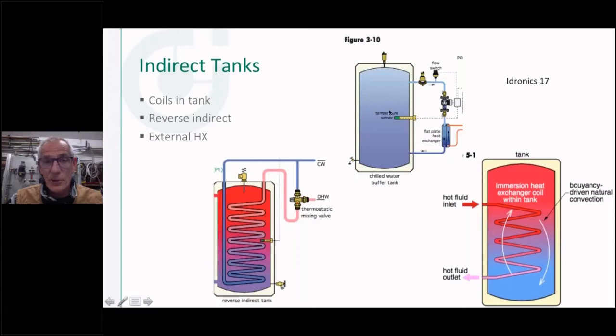So this becomes your thermal storage, your battery, so to speak. And then the plate heat exchanger just pulls out whatever rate of heat and whatever temperature you need out of that. This happens to be a chilled water tank that we're doing cooling out of, but the same concept applies there. And this is probably the more standard, more common indirect type, where the fluid from the boiler would go through the coil in there and come out and would heat the tank.